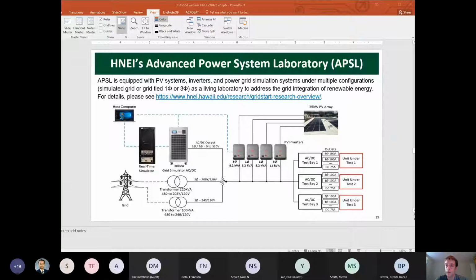And in Hawaii, there are different interconnection rules. The earlier ones were net metering, so whatever excess you produced over top of what you needed would just be exported, and of course that would have impact on voltage directly. Then there's evolution towards customer self-supply, which means that you're not allowed to export at all. So if you can produce much more PV than you need to use, you need to have your PV inverter curtail that energy and not actually produce in the first place. And then the other one is customer grid supply, where you can put power out onto the grid, but you're not paid as much for that power as the power that you buy from the grid, right? With customer grid supply especially, it starts to become an incentive for the customer to try to match their load with their PV production. So there's a little bit of incentive there to start moving that direction.